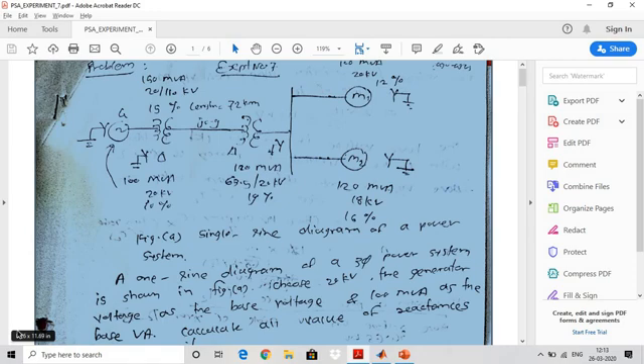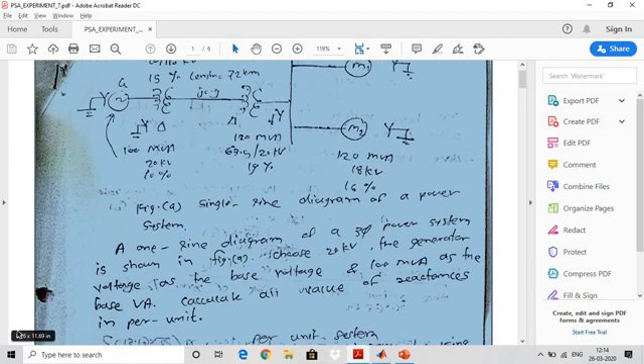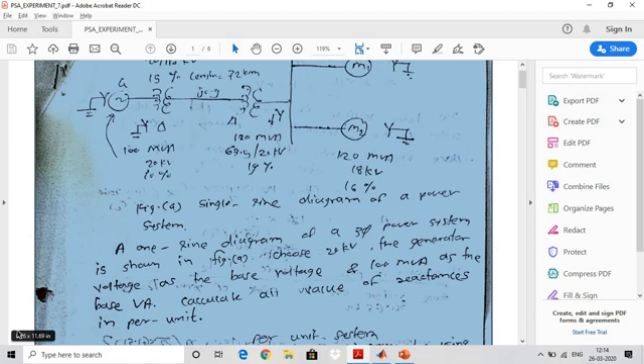We will consider a simple system in which one generator is connected to loads — motors M1 and M2 — through two different transformers. We have to use the per unit system for calculation of different parameters. A one-line diagram of the three-phase power system is shown in the figure. Regarding base values, we choose 20 KV as the base voltage and 100 MVA as the base power. For per unit calculation, the base value of voltage changes as per the transformer ratio, whereas the base value of power remains the same throughout the system.